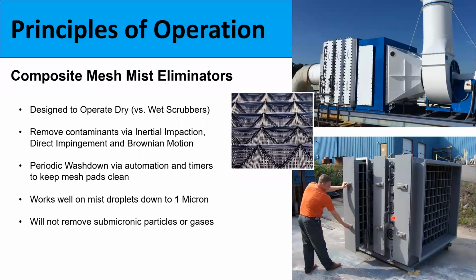So next we have our mist eliminator units. These units typically utilize mesh pad assembly and they operate dry, to remove the entrained droplets via inertial impaction, direct impingement, and Brownian motion. In addition, these units can also operate wet using either manual or automated periodic spray washdown cycles to help clean the mesh pads. These mist eliminators are typically designed for 10 micron and larger removal efficiency, but we can go as low as 1 micron in certain applications.